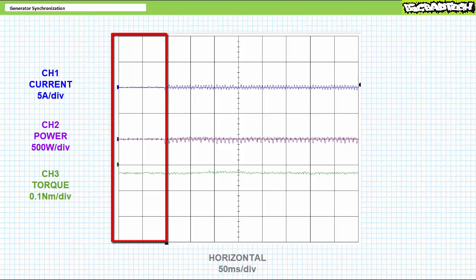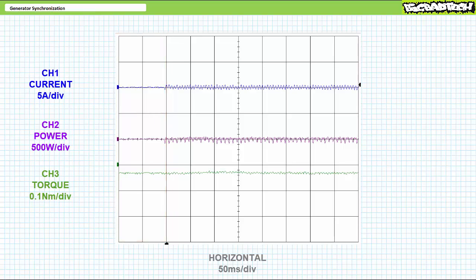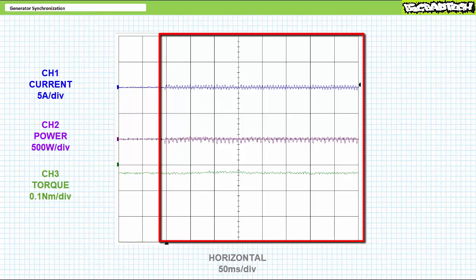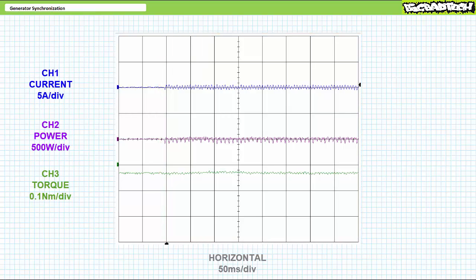When the contactor is open, no current flows into the contactor, the generator exports no electrical power, and the generator produces a token amount of negative counterclockwise counter torque in opposition to the clockwise moving prime mover, accounting for friction. At the time when the phase sequence, frequency, phase shift, and voltage magnitude of the generator matches that of the grid, I close the contactor, and nothing happens. There's no current surge into or out of the generator, there's no massive exchange of electrical power, nor does the generator experience an oppositional braking or motor torque. It's not dramatic, and that's the point. The generator and grid match each other at the moment of synchronization.